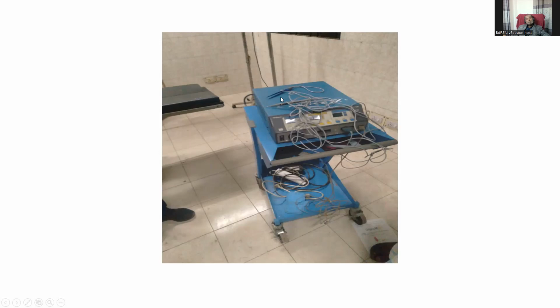So for this machine, the dangerous thing is that after repair, we need proper grounding. If proper grounding is not done by our engineer's calibration, there is a problem with the stainless steel. And if the line fails and comes to the electronic board, then the whole machine will be electrified. If anybody touches it, they will be shocked. So we need to calibrate it and we need to make a guideline. Already we have built the guideline for every hospital. And in that case, if there is a stoppage, we have the tripping. After repair, the tripping is corrected.